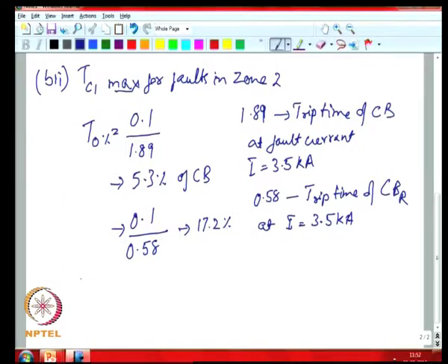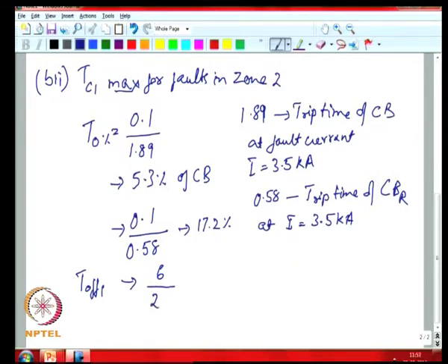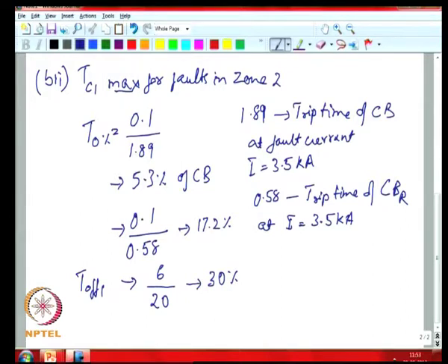If you look at the Toff1 duration of 6 seconds and the reset time for breakers CB and CBr is 20 seconds, the breakers would reset by 30% in a 6 second duration. So both CB and CBr are fully reset by the end of the off duration.